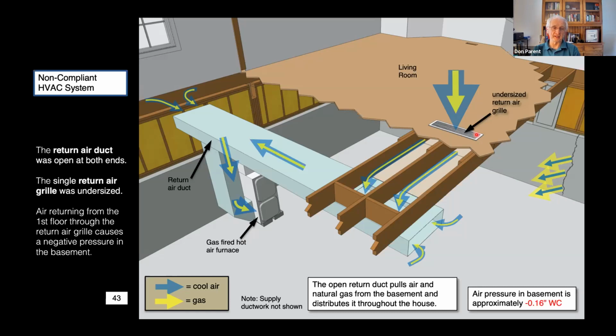That combined with the fact that the return air duct in the basement was actually open on both ends. It should have been sealed off. The building code requires the ductwork to be fully closed. It wasn't. And so we had a situation where the return air was going through the return grill, which was a factor of 3 too small, causing a pressure drop. We knew what the flow rate was because we knew the specs of the furnace. And so we knew the pressure drop was about 0.16 inches of water column to the negative. So basically we were creating a vacuum in the basement because the furnace was sucking air from the basement.